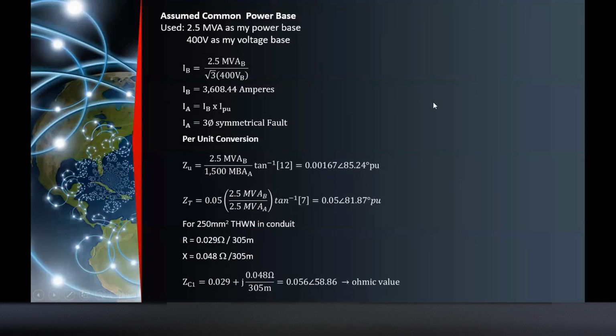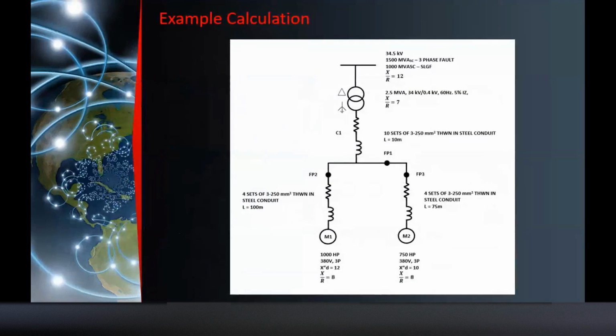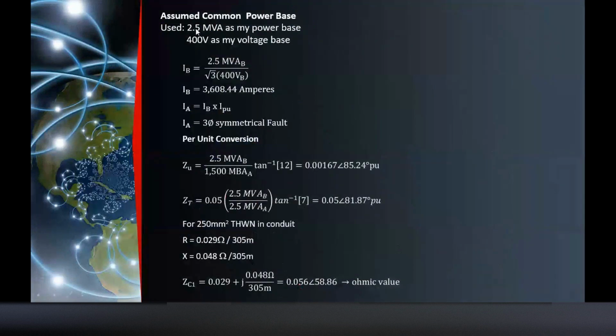So, as I said earlier, when I assume a power base, I use the transformer itself, the main. Here you will notice, assume a common power base. When you assume, use the same base all throughout your calculation. I used my own; you can use anything, no problem. I used 2.5 MVA as my power base and 400 volts as my voltage base. This is the rating of the transformer and this is my secondary voltage rating.